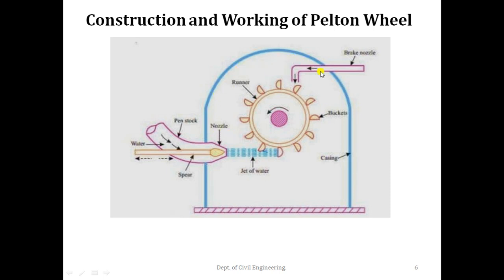The Pelton turbine is provided with a casing to prevent splashing of water and to discharge the water to the tail race. When the nozzle is completely closed by moving the spear forward, the amount of water striking the runner is reduced to zero. But due to inertia, the runner continues revolving for a long time. In order to bring the runner to rest in a short interval of time, a brake nozzle is provided. This brake nozzle directs a jet of water that hits the back of the vanes of the turbine — this jet is called the braking jet.